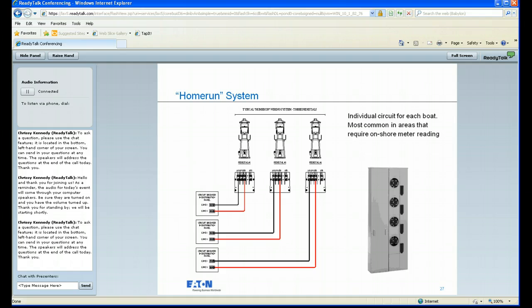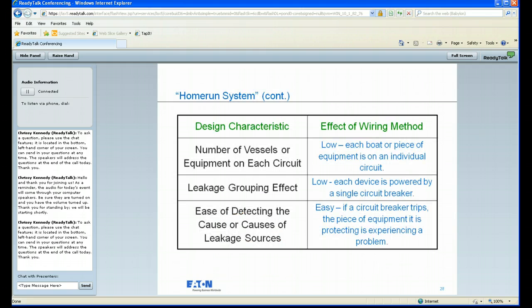The next system is what's called a home run method. Typically that means you have one circuit breaker for one pedestal or one circuit breaker for every 2 boats. Very common in areas that require onshore, but also it's a personal preference. I know we do some work with electricians that like to have all of their power pedestals on one circuit breaker, simply because if there is an issue with a breaker or with a boat, you're going to have only a couple of boaters without power if there needs to be any kind of repair work done. The same applies with the monitoring system. If you've got one boat that's particularly causing a problem, it's much easier to identify on this home run system where you only have to worry about one or two boats being powered off of a single protective device.